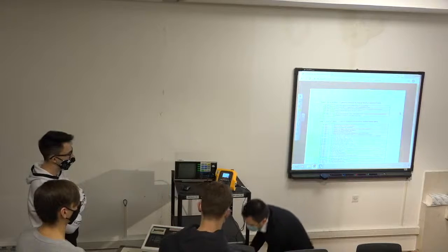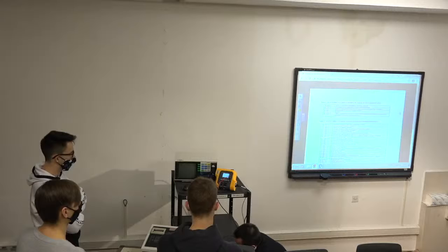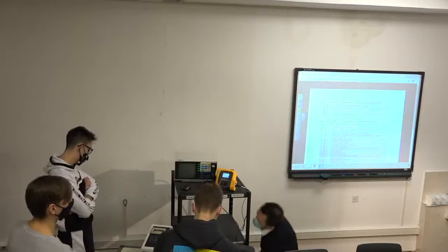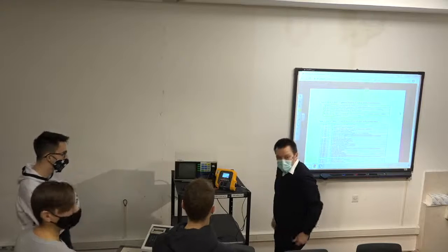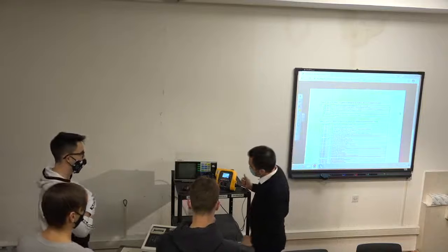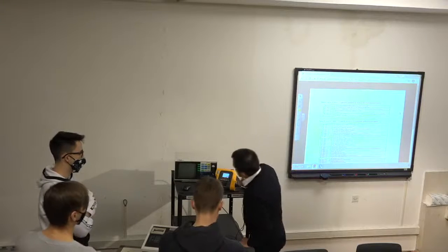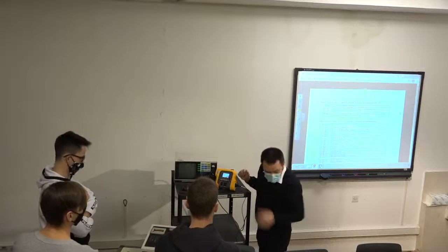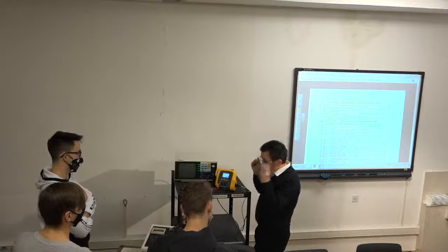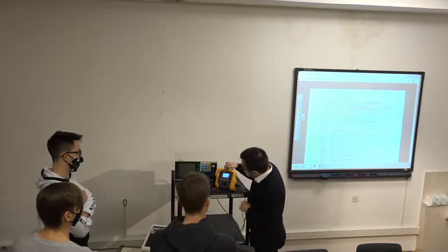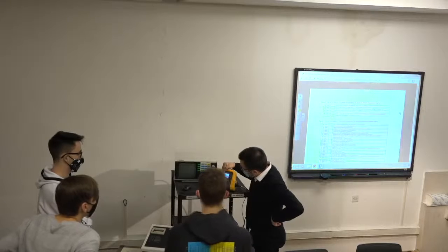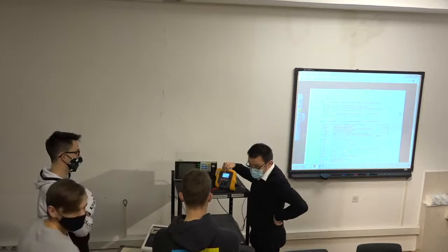So I will now go again to the self-testing, and then we will make both. Yeah, okay, so the first choice that we have to make is actually the choice of a standard that we will be, let's say, obeying. In this case, you have the American standard. AAMI is American Association for Medical Instrumentation.